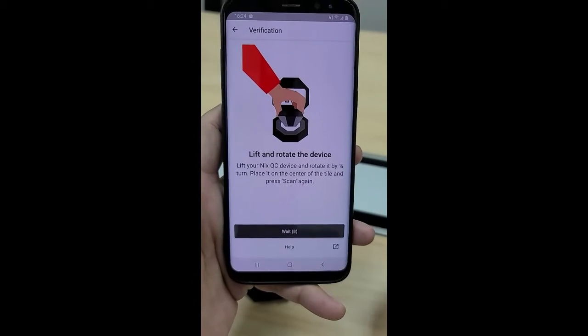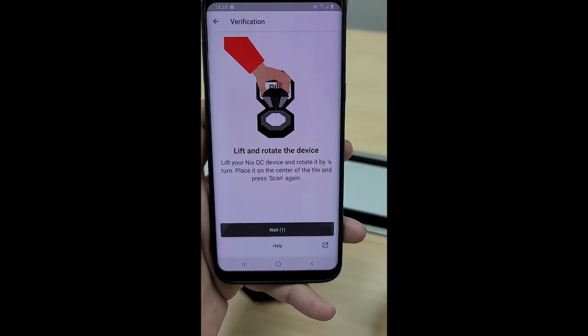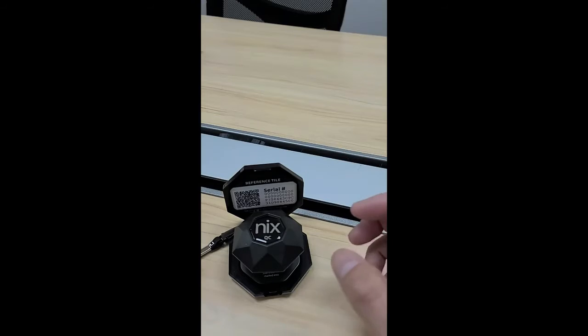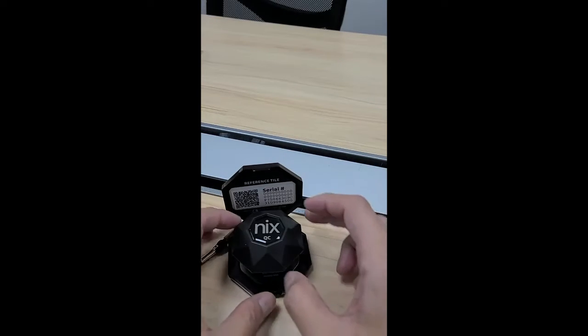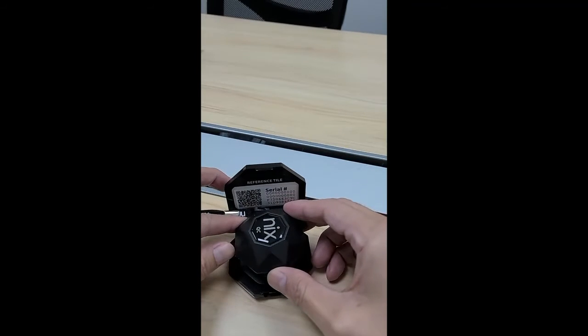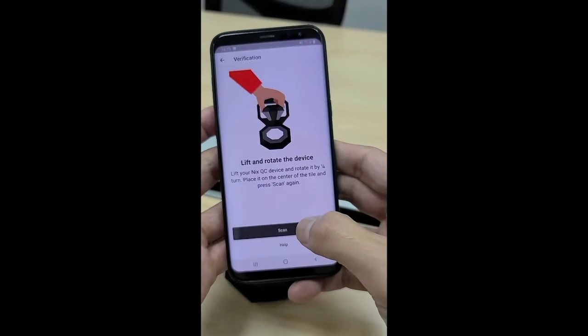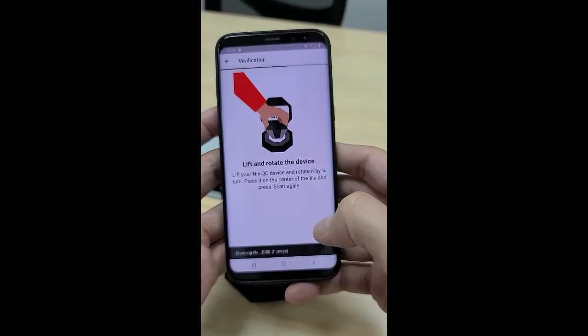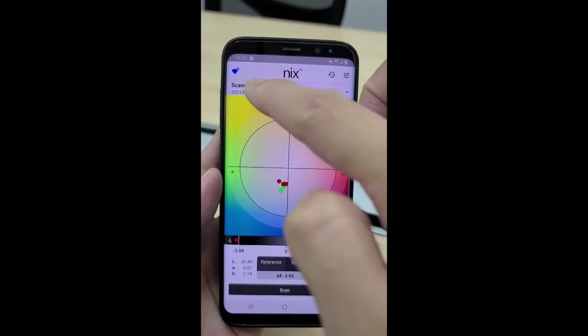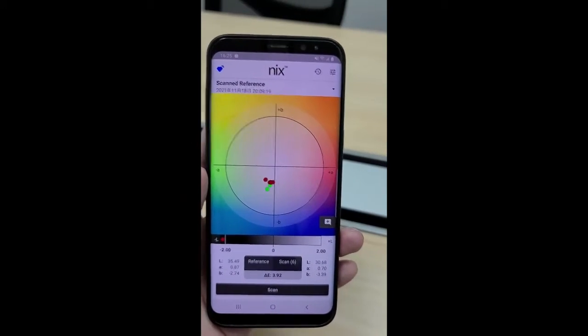The following instruction tells you to lift the Nix QC and rotate it by one quarter turn. Follow what it tells you to do — rotate by one quarter turn, then press Scan again. Once done, press the Finish button. The warning icon disappears and we can start measuring.